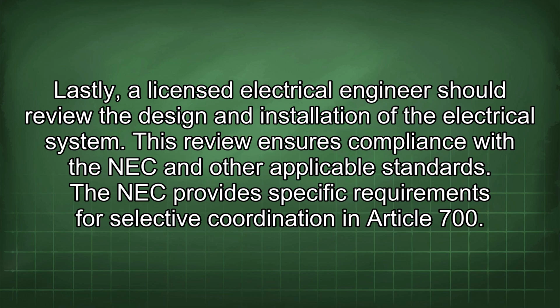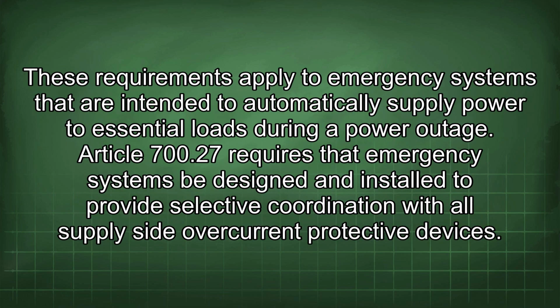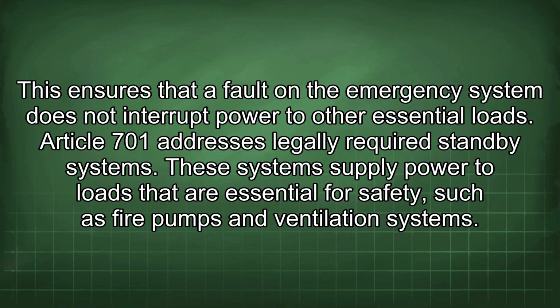The NEC provides specific requirements for selective coordination in Article 700. These requirements apply to emergency systems that are intended to automatically supply power to essential loads during a power outage. Article 700.27 requires that emergency systems be designed and installed to provide selective coordination with all supply-side overcurrent protective devices. This ensures that a fault in the emergency system does not interrupt power to other essential loads.